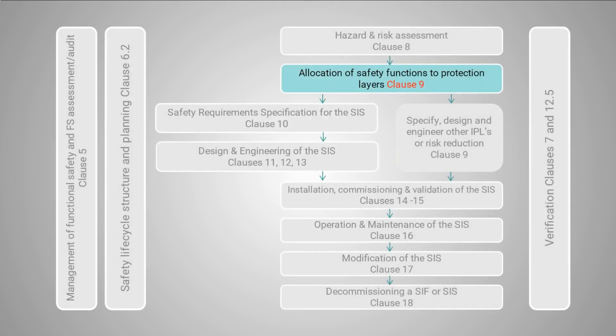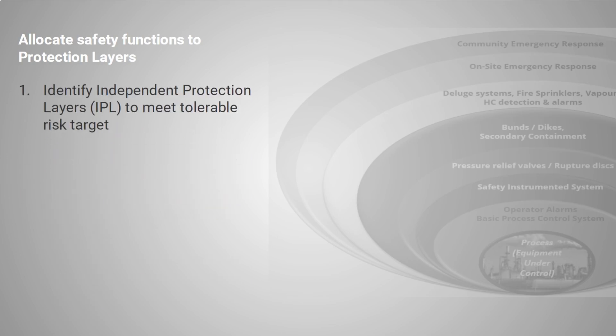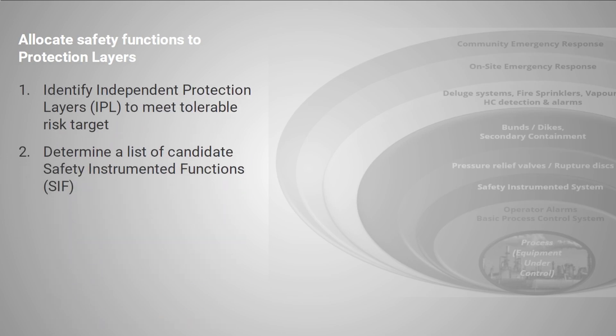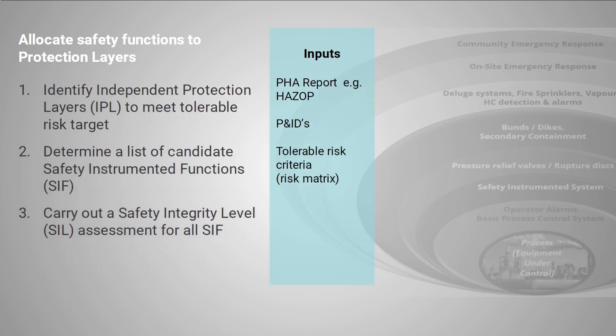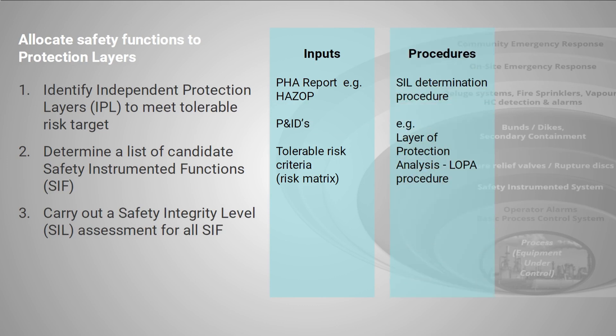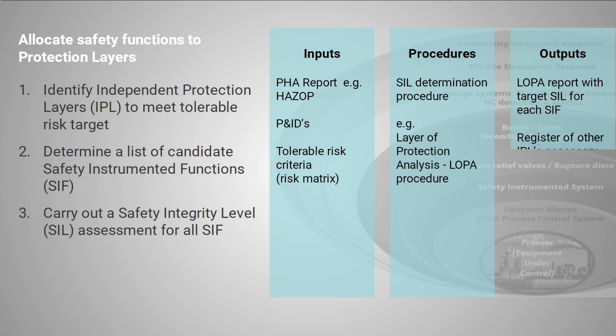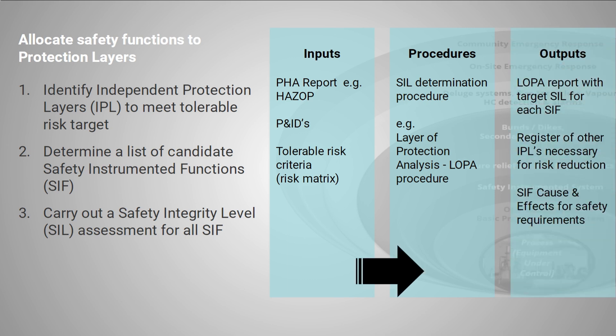After hazards and safeguards have been identified, there needs to be some further analysis of risk reduction measures. An effective technique for this is LOPA, Layer of Protection Analysis. This can allocate risk reduction to different layers, considering active and passive measures, and can eventually result in selecting SIL for functions within the SIS.